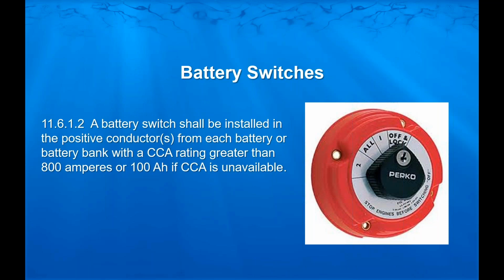Battery switches. We need a way to control one of our other components in our circuit. A lot of people question when you don't need a battery switch. Well, it's spelled out pretty plainly in E11. A battery switch shall be installed in the positive conductor from each battery or battery bank with a CCA rating greater than 800 amps or 100 amp hours, if you can't or don't know the CCAs.